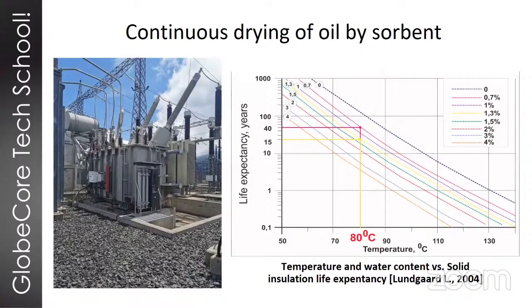So for the first method, what we're going to talk about is drying of transformer with the sorbent. And this method, on the one hand, can be called a preventive method because it reduces or maintains a certain humidity level in solid insulation during the transformer operation. On the other hand, this method can also be classified as an indirect drying method because its effects on the solid insulation are facilitated by its effects on the oil. So in a way, it indirectly impacts the solid insulation.